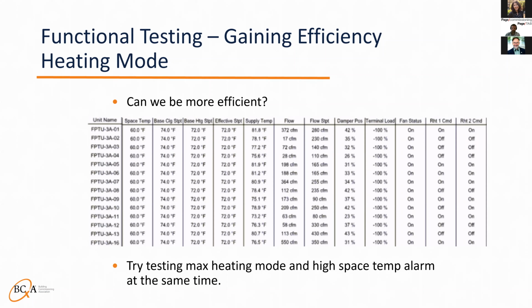This will tell you your temperature differential across the heating coil, and from there you can calculate capacity with a sensible heat equation. You also have the ability to compare all of the terminal units together to see if one is lagging behind. It's good to do this with all types of reheat, but especially for hot water. It can help you discover coils that are clogged, isolation valves are closed, or possibly coils that are piped backwards. Whichever temperatures you see lower than the others are worth adding to your sample to visit in person.